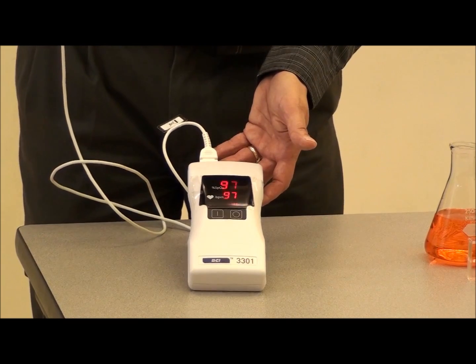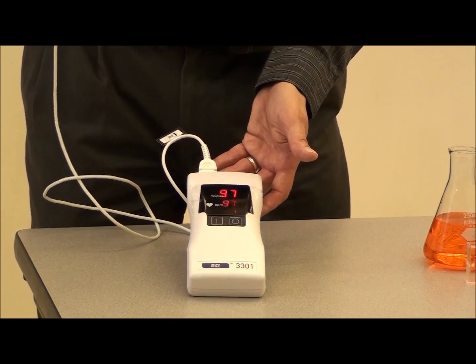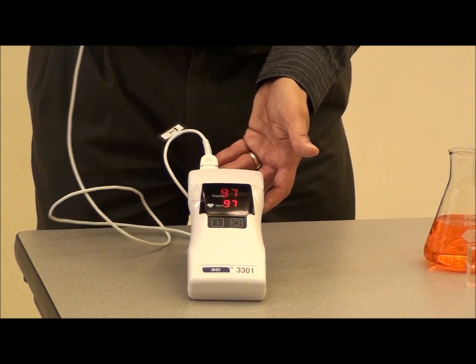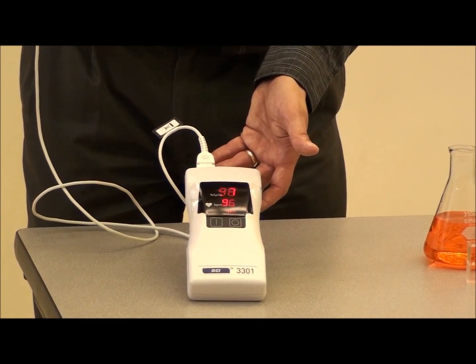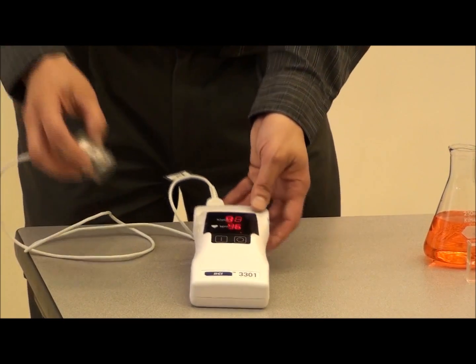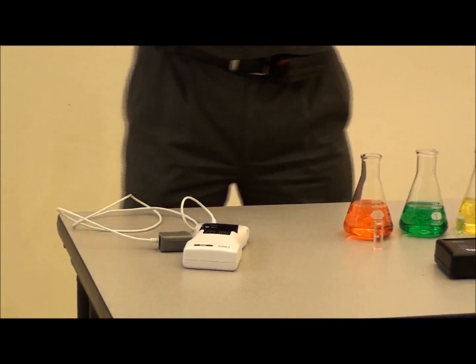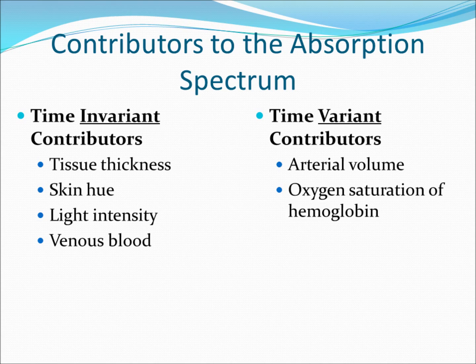In order to properly measure the oxygen saturated hemoglobin percentage, the oximeter must accurately remove those contributions to the absorption spectrum that are constant in time. These constant contributions would be, for example, from the thickness of the tissue in my finger, skin hue, light intensity, and venous blood. Removal of the time-invariant contributions to the signal will leave those contributors that vary with time, including the arterial volume and the oxygen saturation of hemoglobin. This allows the pulse rate to be measured and subsequently the calculation of the oxygen saturation.